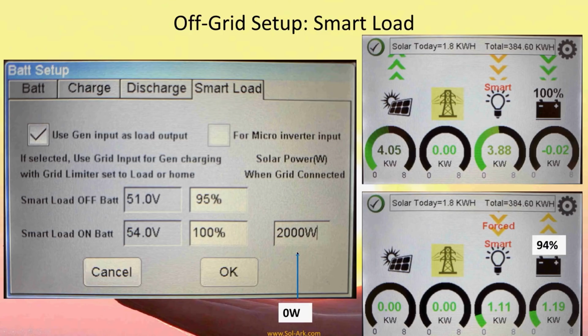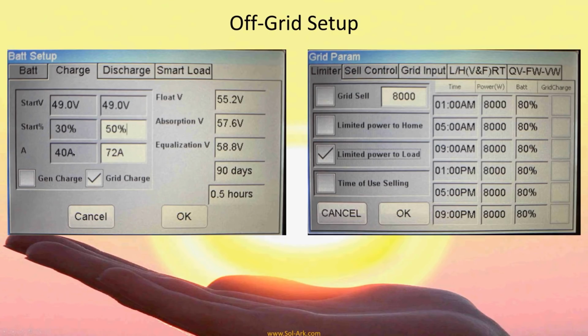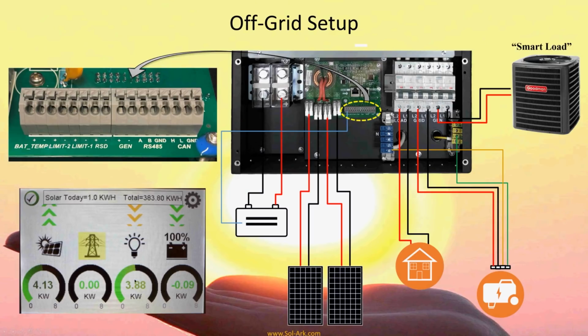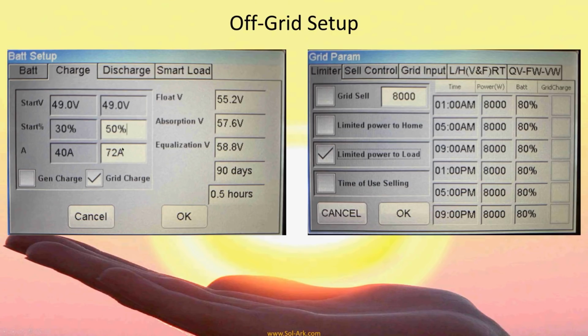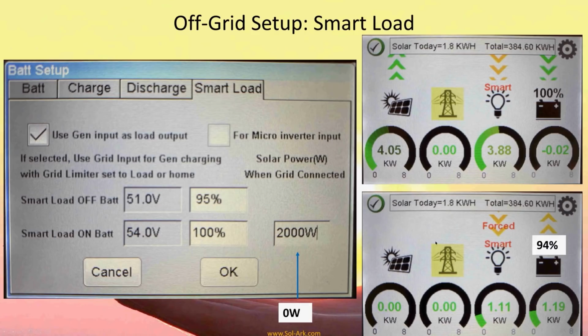It's for really time shifting. But I would turn it to 0 for off grid, because if I want to turn on my generator, I want my smart load to turn on too, because I'm hooked up to a generator. And I forgot to mention here that as our loads go up in terms of this loading from the generator, it will decrease the charging value so that we're not overloading our generator or our grid breaker. So it's pretty smart.